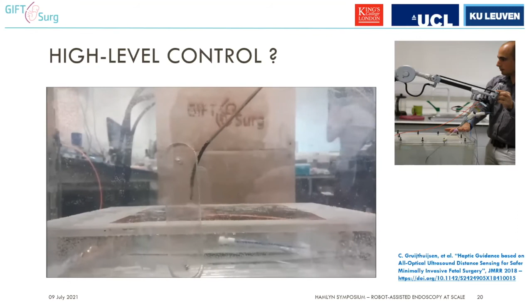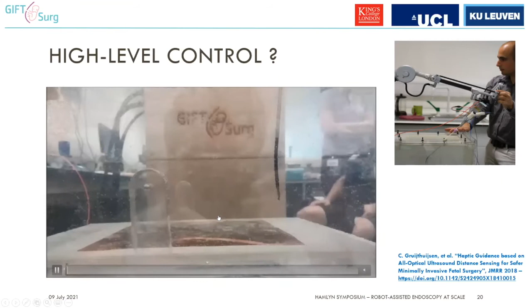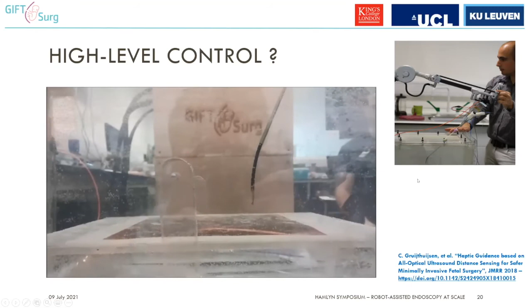So what becomes important if you are developing such flexible instruments is that you think of ways to mask this complexity. And so here on the video, you see how we autonomously control this distal tip. We have a sensor inside, and the sensor measures the surface, estimates the normal to the surface, and then based on that, we control the bending angle automatically. And this kind of low-level task is taken over, and the surgeon doesn't need to care about that. Here we cheated a bit because we had a sensor in there, an all-optical ultrasound sensor.